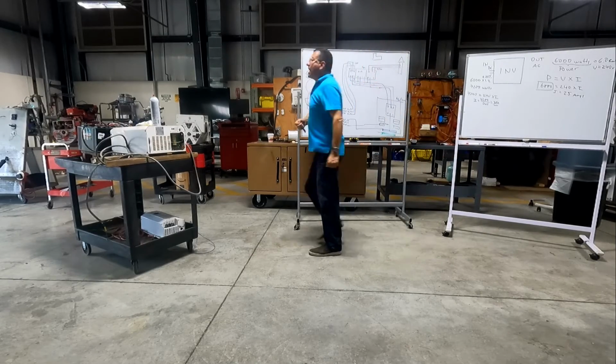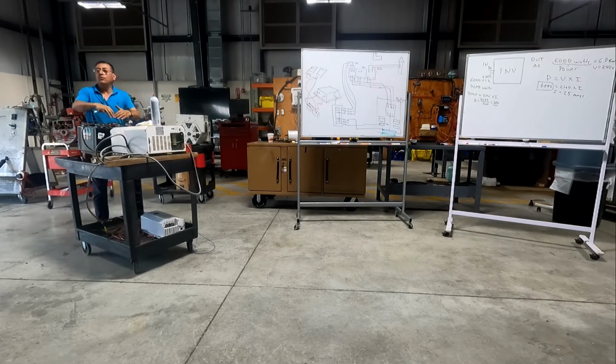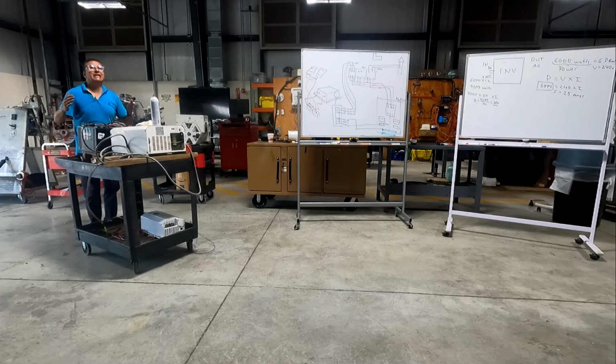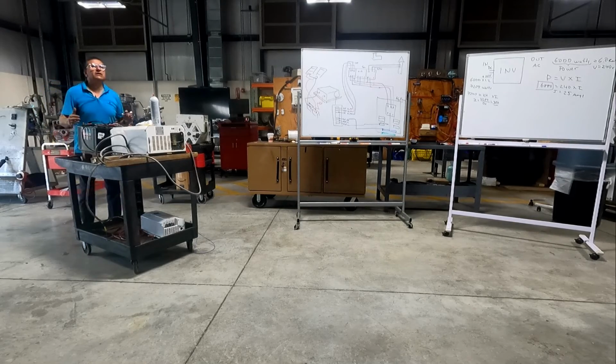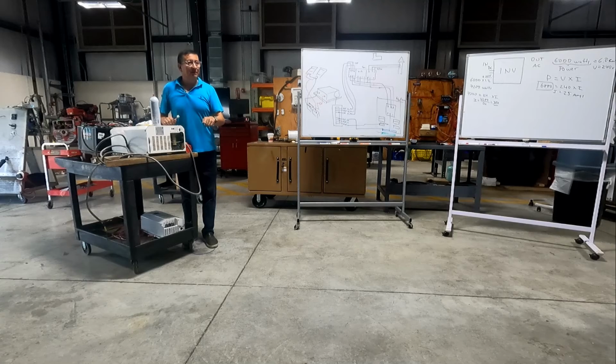If I have a battery bank configured in 24 volts, okay, look at this. If I have a battery bank with a capacity of 300 amps, this plus this plus this plus this is 300 amps, I can produce here 7,200 watts for 1 hour.